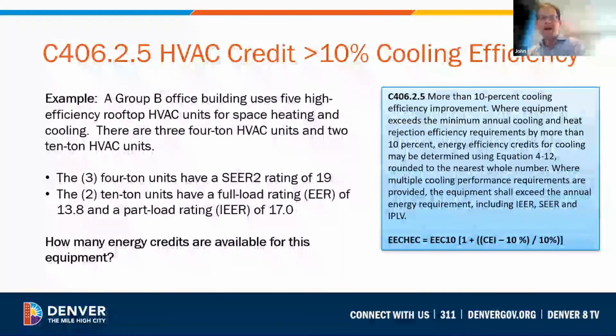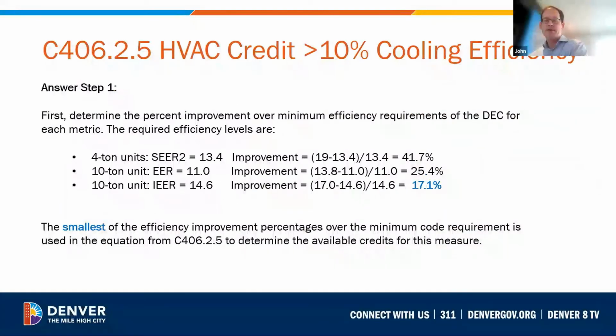Now note, for a system that has multiple ratings, say a larger 10-ton rooftop unit that has both a full load EER rating and a part load or IEER, integrated energy efficiency ratio, rating, both of those ratings would have to exceed the minimum thresholds by that given percentage to receive that credit. So this shows the example, where you would calculate the improvement relative to the minimum efficiency requirement applicable to that equipment class of product.